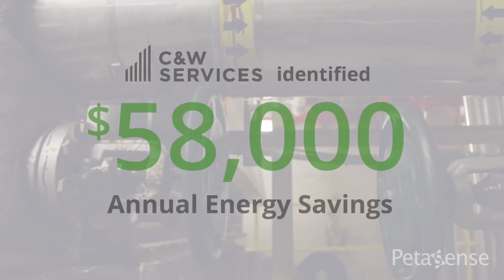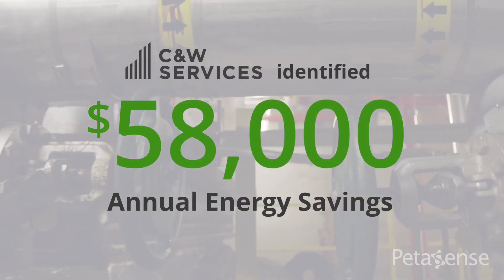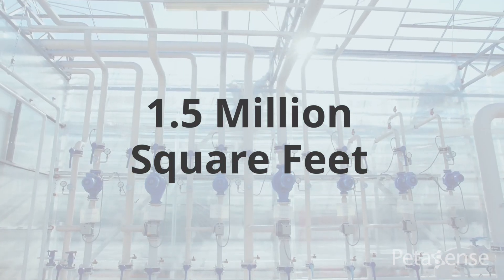We can actually truly identify what we're saving — it was about $58,000. We can identify proper working of the steam traps without failure. One steam trap failure is not going to cause that big of an issue, but when you have a site as large as ours — 1.5 million square feet roughly — if you have 10, 12, 14, 30 different steam traps failing, it causes a lot of problems.